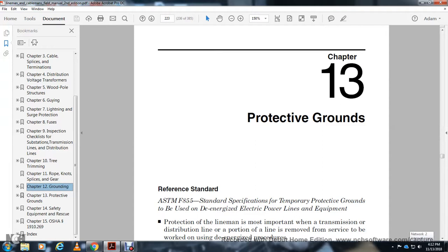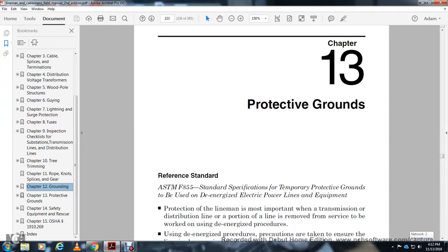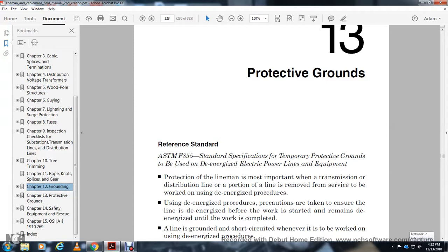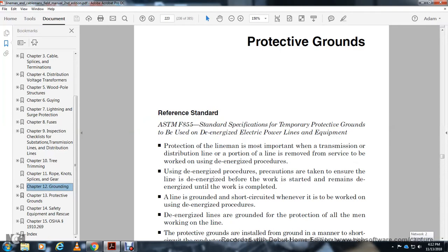Protection of the lineman is most important. When a transmission or distribution line, or a portion of the line, is removed from service so that it can be worked on, the de-energizing procedure is used. Precautions are taken to ensure the line is de-energized before work is started and remains de-energized until the work is completed. The line is grounded and short-circuited whenever it is to be worked on using the de-energized procedure. De-energized lines are grounded to protect all the men working on the line.